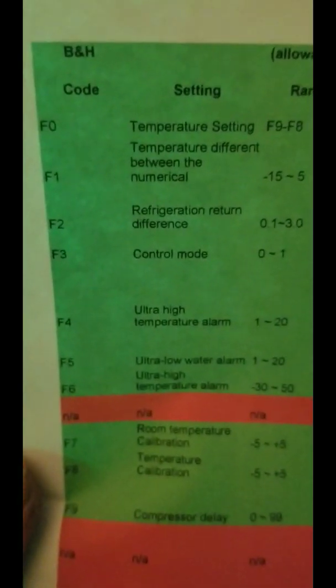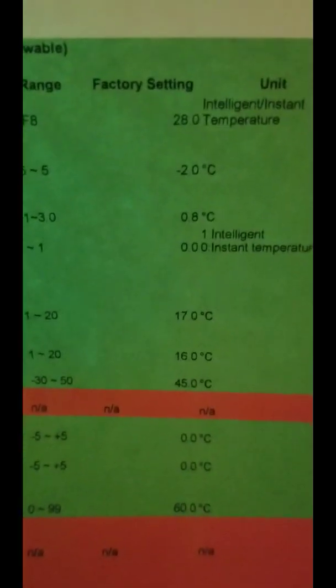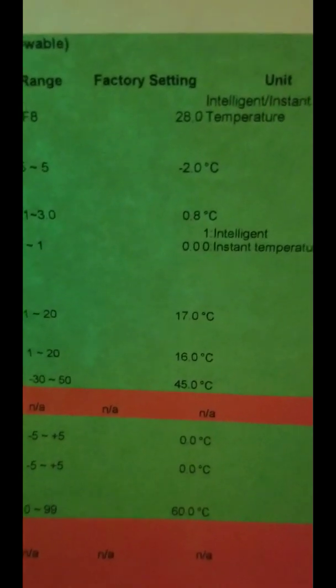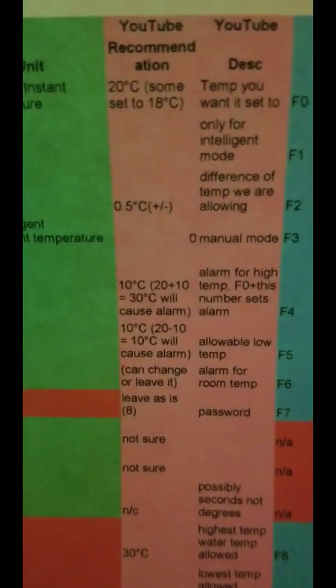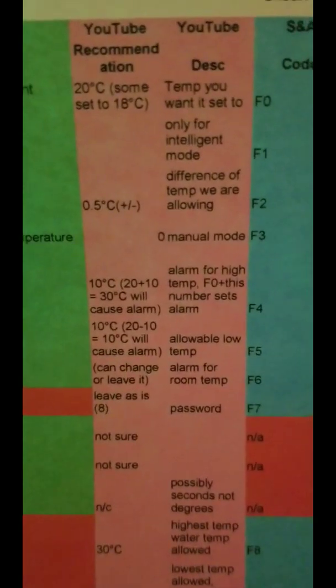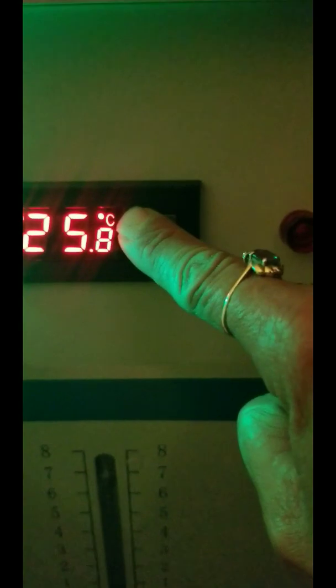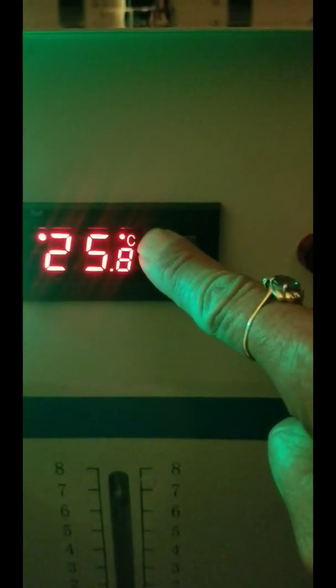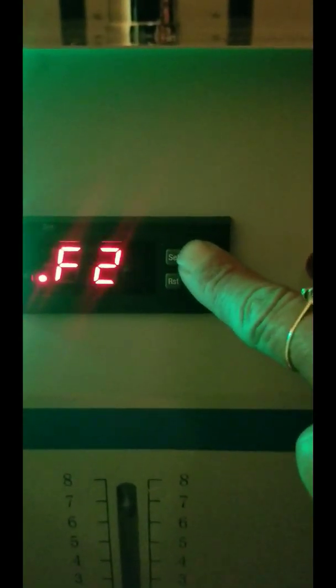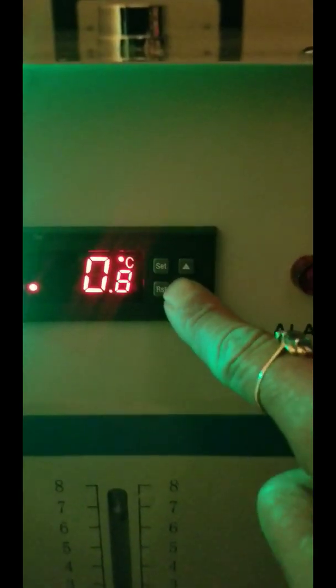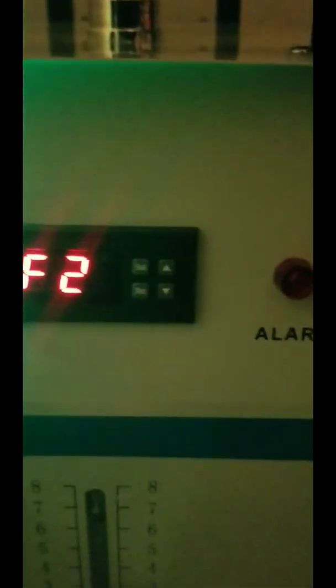The next one is F2 — refrigeration return difference. The default is 0.8 degrees Celsius, and we're going to change it to 0.5. It's the difference in temperature we are allowing, so plus or minus 0.5 degrees. Go in, press SET, navigate to F2, press SET to select, change it to 0.5, and press SET. Done.